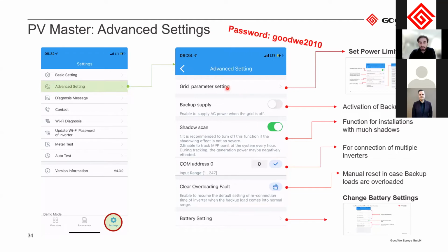From this one, this thing here will pop up. And usually both when you enter basic and advanced settings, they will ask you for a password. The standard password is GoodWe 2010. It's important to remember. This is also described in the manual, and it's also recommended to change this afterwards so that no one can access the settings that shouldn't. In the advanced settings menu, you have the grid parameter settings here, and here you can set the power limit. We'll show that later. Or maybe let's do it straight away.